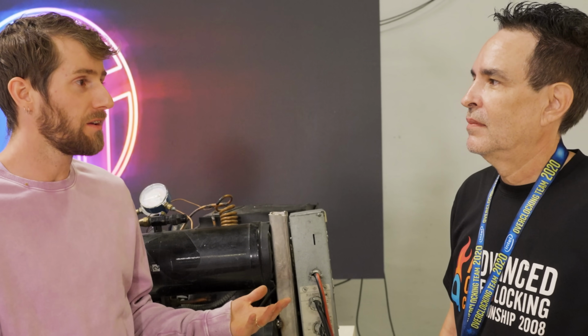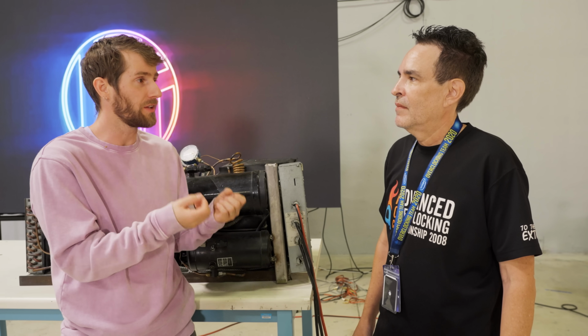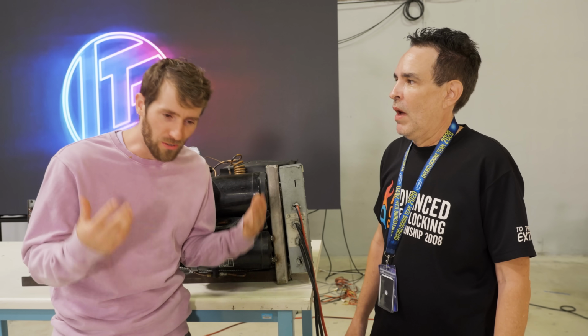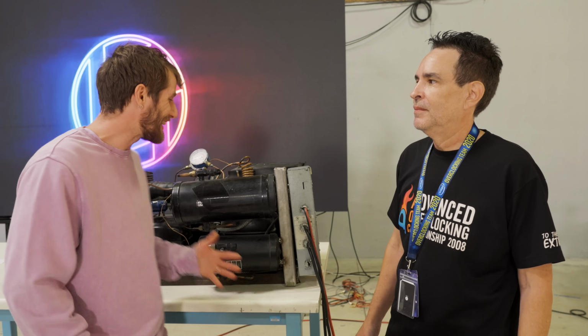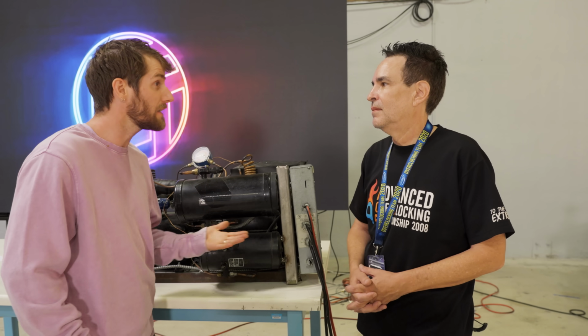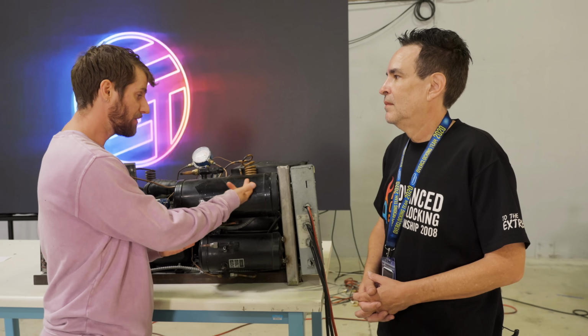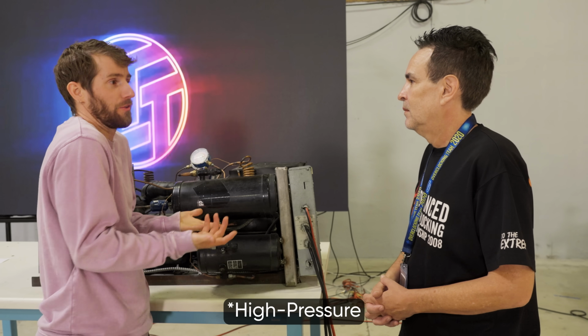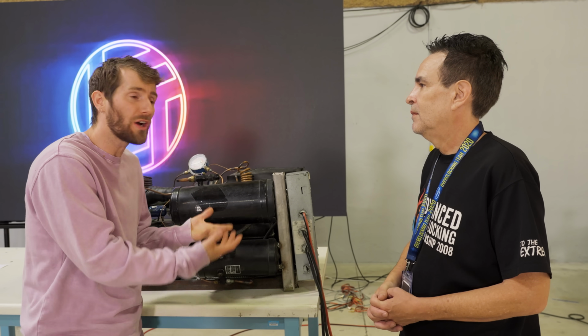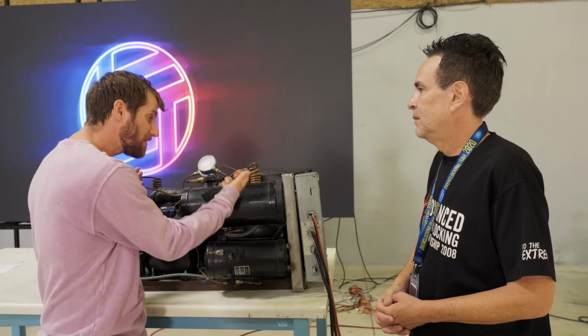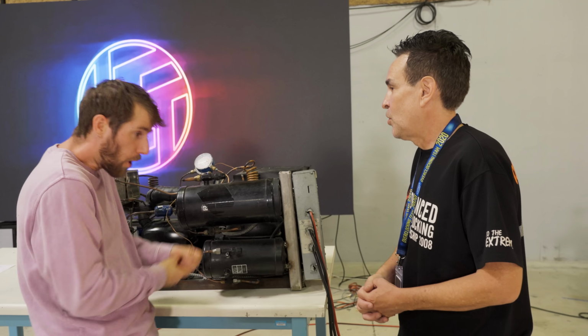But when you weren't running it, the pressure would be astronomical because it's all in gaseous form. Right, I had to put more gas in the system and the pressure would go up higher, and I couldn't run into that. So this just gives us enough volume. Realistically, when we're running, this isn't like high density gas storage, because so much of it is in liquid form, but it gives the gas somewhere to go when it's all turned off and it becomes gas. Okay, I think we got it. Great explanation.